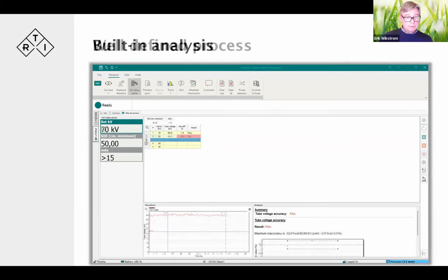As we advance, here's something that, from a real good distance, we see that something is amiss. Something is wrong. We have a red signal here. It says fail. We look also at the analysis. It says fail, and it says maximum inaccuracy here at 60 kV. It's outside the limit of ±5, which we have designed into the template. So it's failing because we're outside that pass-fail limit.